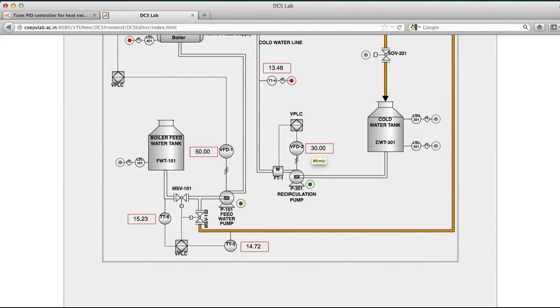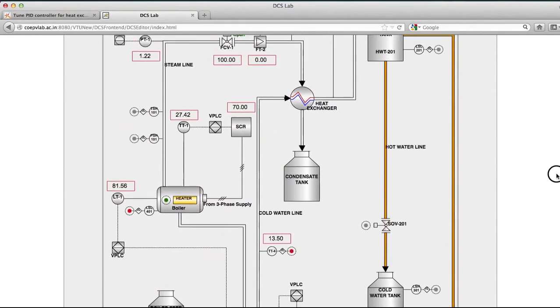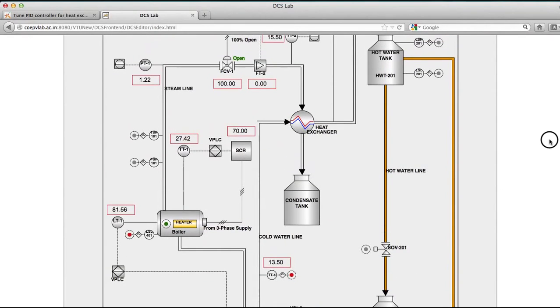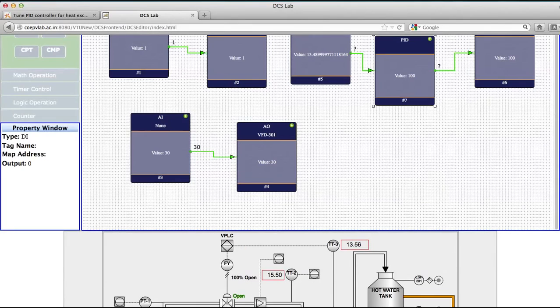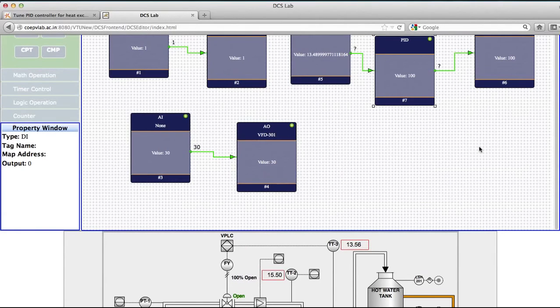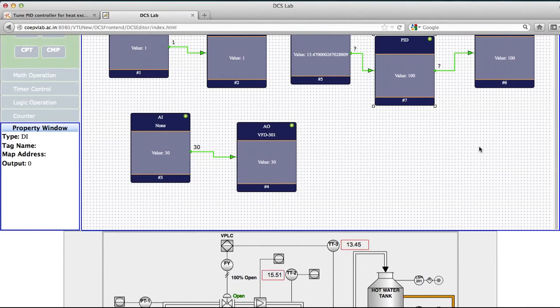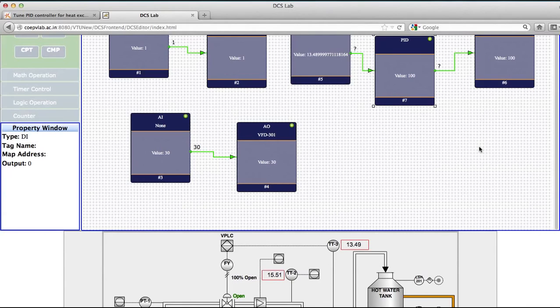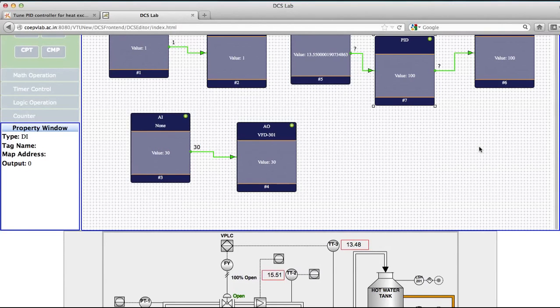Now what will happen? This will go on working. The temperature will go on rising. We will monitor this temperature. After you receive the temperature equivalent to 135 and the pressure of 3.5, you will find that the outlet temperature of the heat exchanger will go above the set point. If your PID tunings are correct, it will get tuned where you will receive error equal to 0.